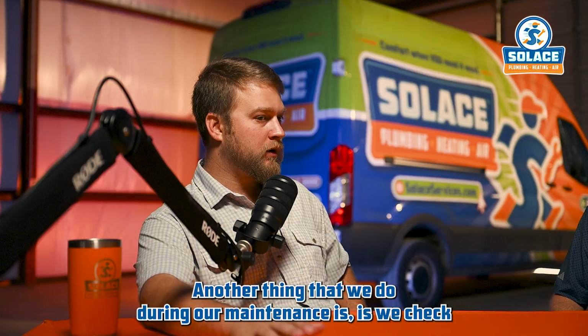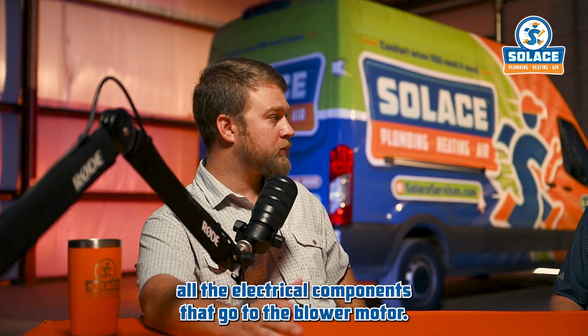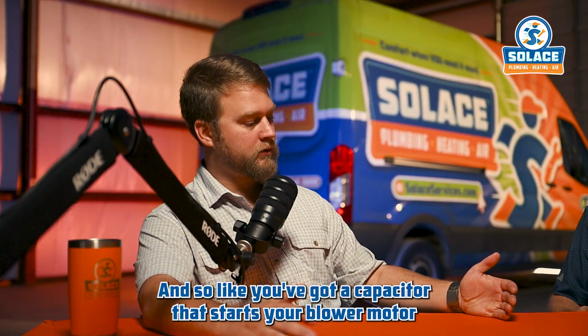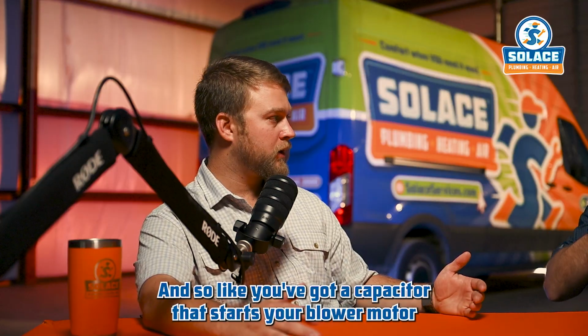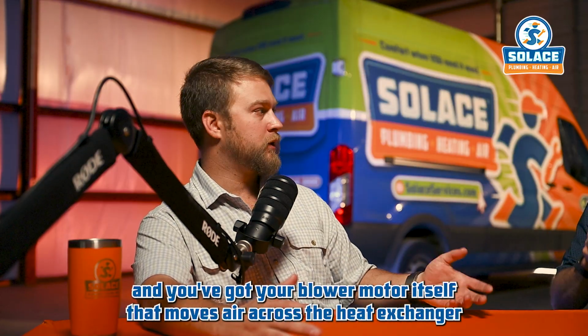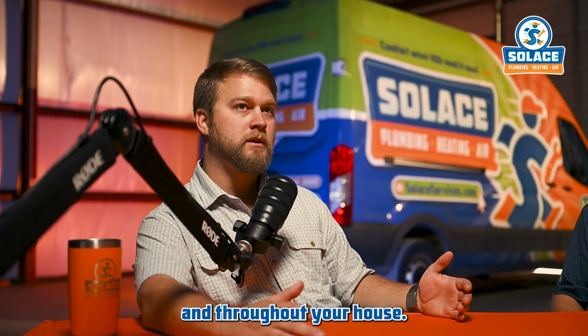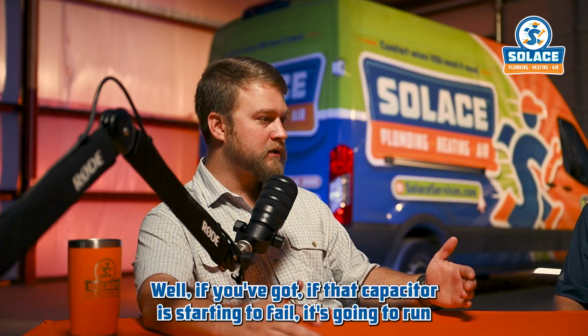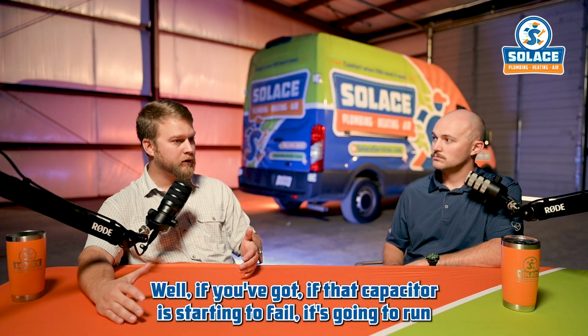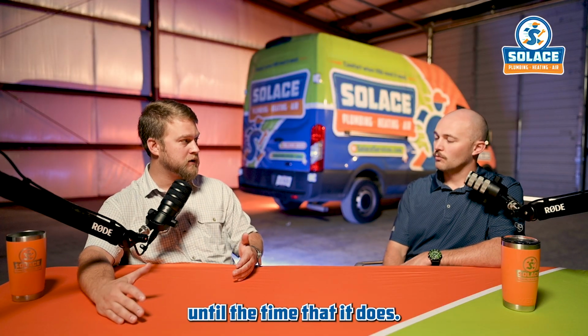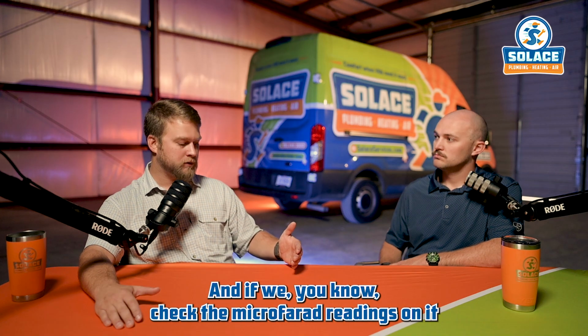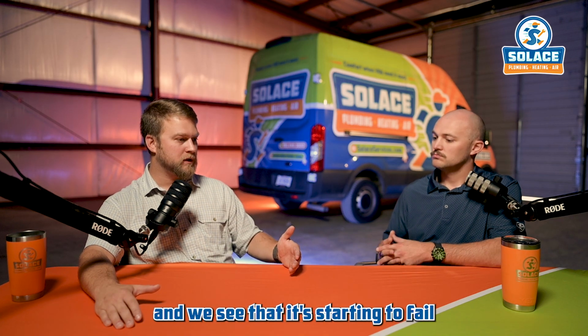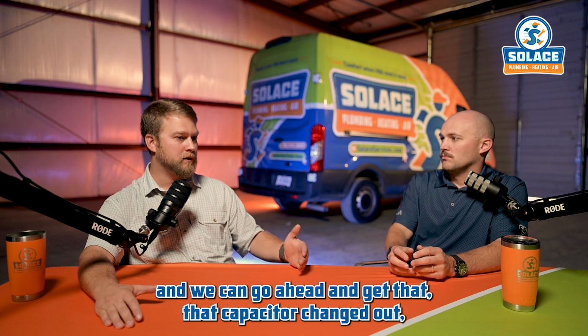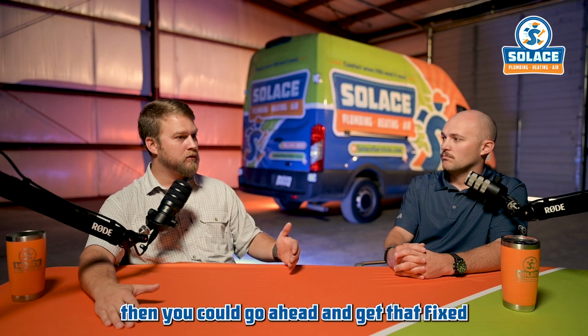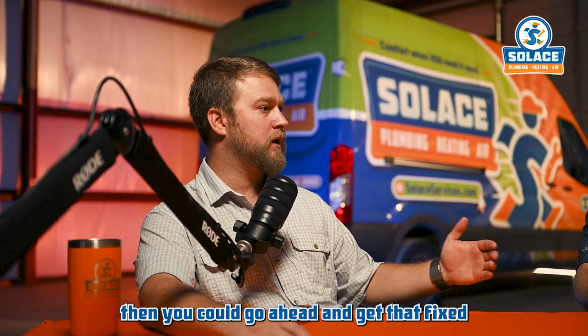Another thing that we do during our maintenances is we check all of the electrical components that go to the blower motor. You've got a capacitor that starts your blower motor, and you've got the blower motor itself that moves air across the heat exchanger and throughout your house. Well, if that capacitor is starting to fail, it's going to run until the time that it doesn't.